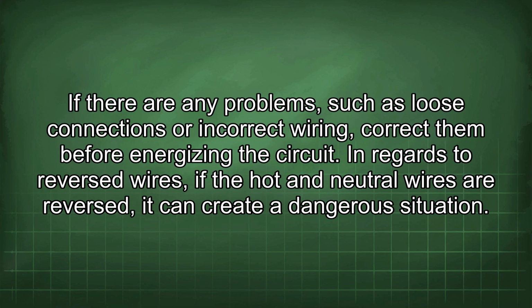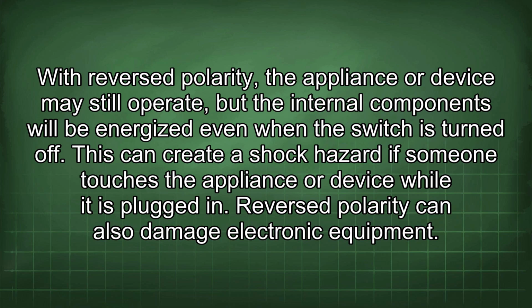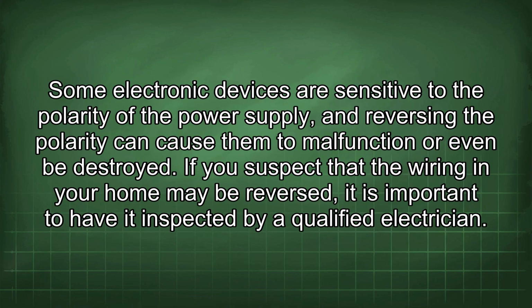In regards to reversed wires, if the hot and neutral wires are reversed, it can create a dangerous situation. With reversed polarity, the appliance or device may still operate, but the internal components will be energized even when the switch is turned off. This can create a shock hazard if someone touches the appliance or device while it is plugged in. Reversed polarity can also damage electronic equipment. Some electronic devices are sensitive to the polarity of the power supply, and reversing the polarity can cause them to malfunction or even be destroyed.